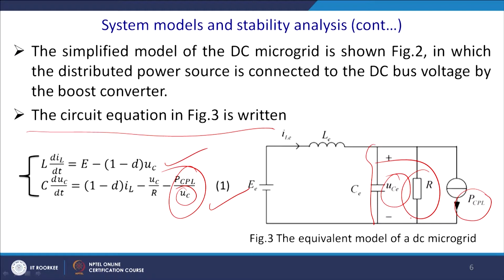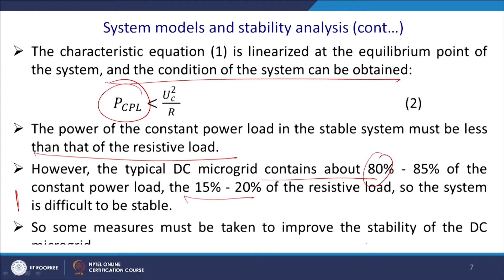However, this is one of the challenges, that a typical DC microgrid contains about 80 to 85% constant power load. You have a huge constant power load, ultimately all the SMPS in your laptops and desktops are constant power loads, and only 20% to 15%, that is the heating load, are resistive. So, it will face a lot of challenges in stability. For this reason we require to take some measures to ensure the stability of the microgrid.